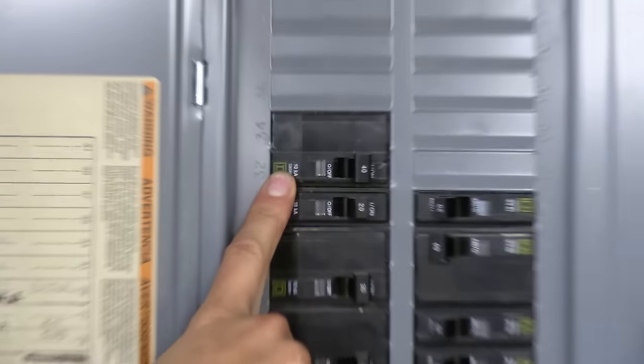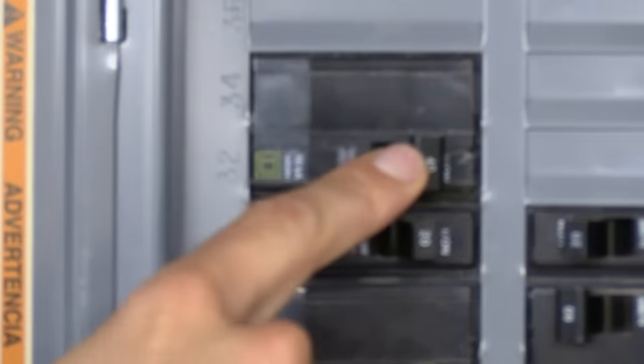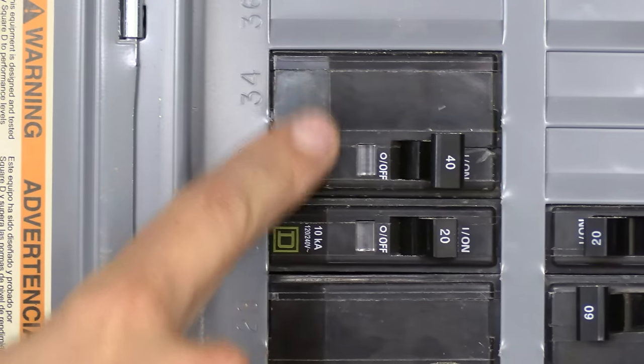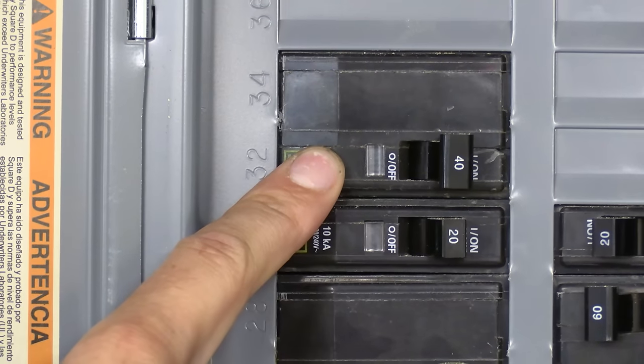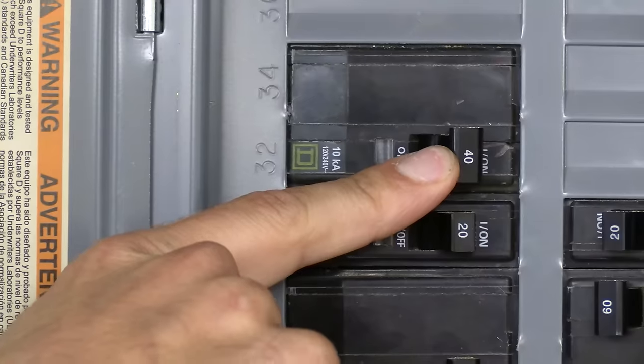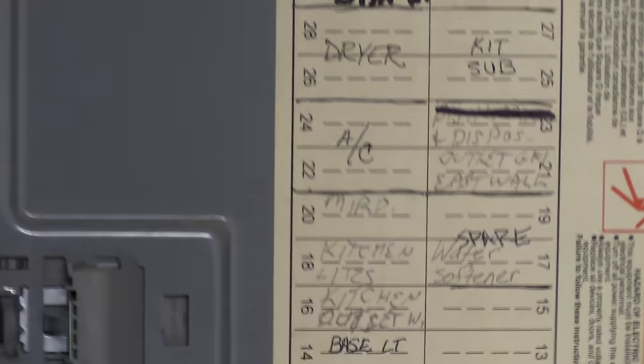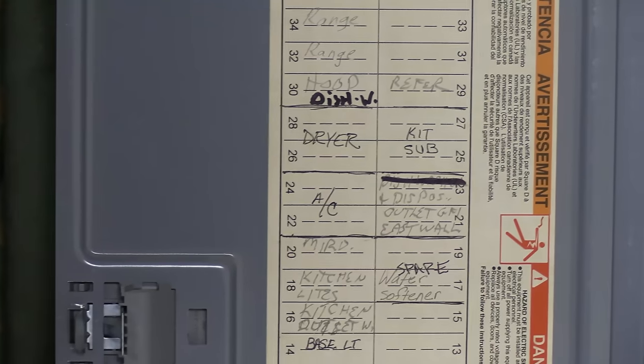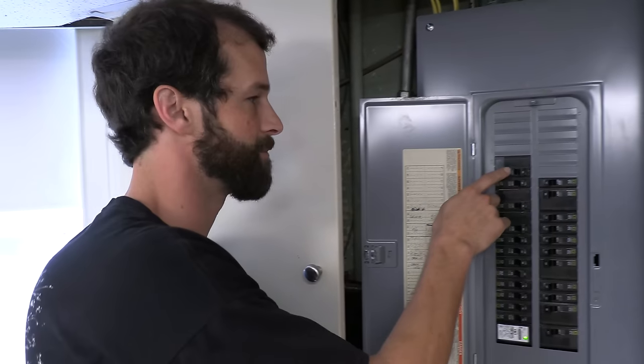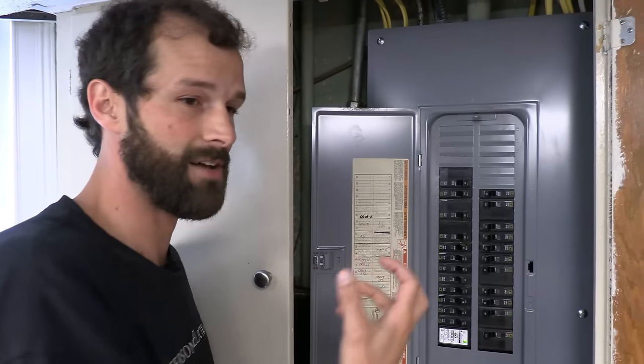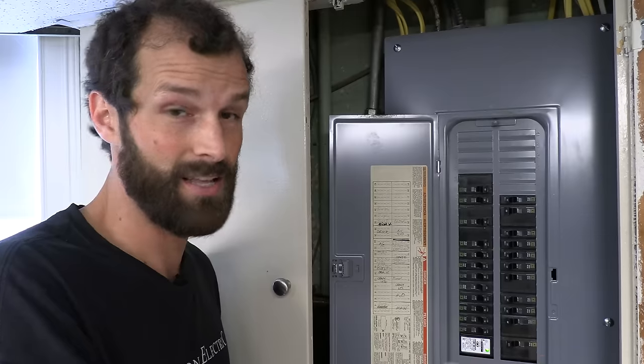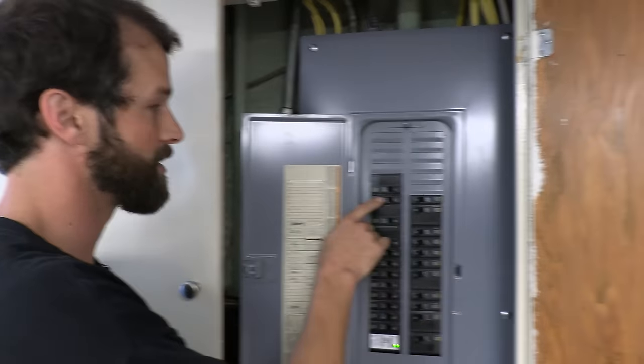If you're not comfortable with panel labeling immediately, let me show you some anatomy of an electrical panel and we'll just go through step by step so that you know the shortcuts to help you quickly identify circuits. A larger breaker like this, this is a two pole 40 amp breaker. It means it's a 240 volt circuit that draws 40 amps. Here on the panel schedule, it says range. However, I don't have an electric range. So I'm wondering if that's the electric oven or there could be an old range outlet hiding behind the gas range that I need to be on the lookout for.